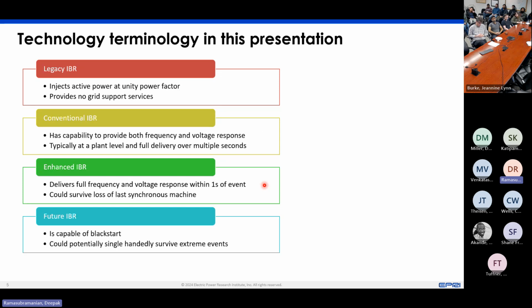Then you come to something called an enhanced inverter-based resource, essentially one where a lot of the services provided at the plant controller level are brought down into the inverter level. Because of that, you're able to provide full frequency and voltage response within one second of an event occurring. There are now requirements around the world asking for this kind of behavior—not necessarily in North America, but other regions with high inverter-based resource penetration have started asking for these fast responses.